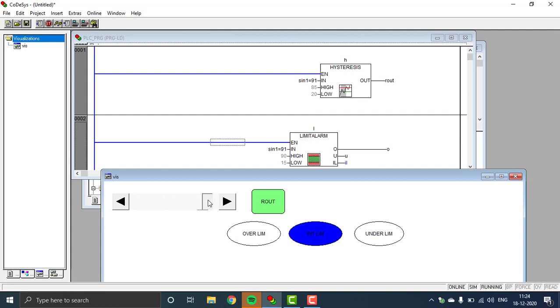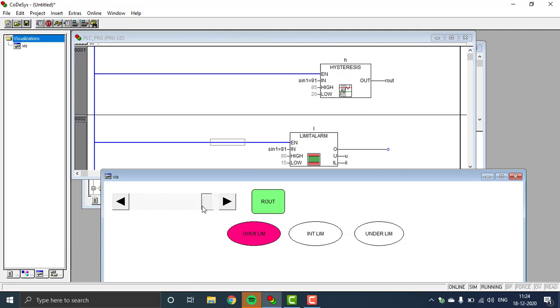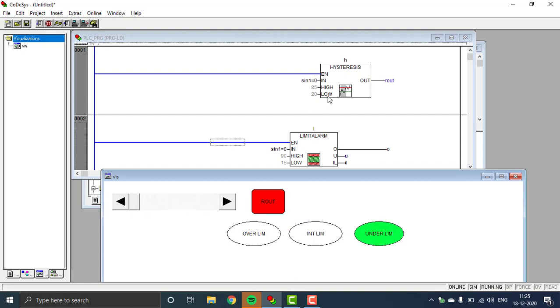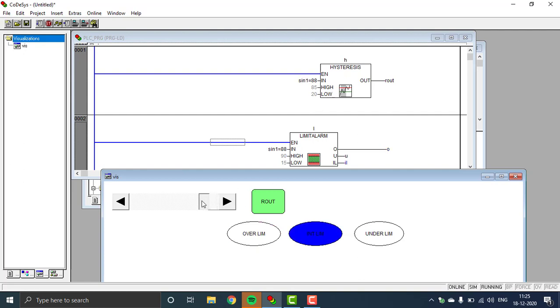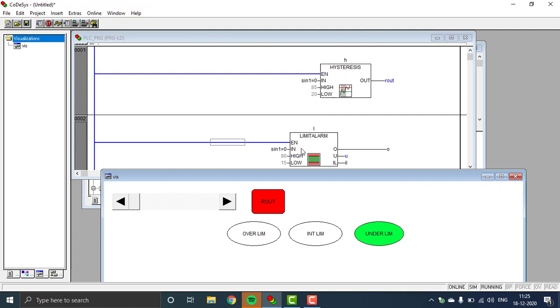Increasing to 93 and the over limit alarm has been triggered. These are all the alarm conditions and the hysteresis output for ABB with HMI visualization. You can see the intermediate limit and under limit also. The relay turns on only when the input reaches below 20 — not even in the 50s, not even in the 40s, only under the 20 limit. That is the ABB hysteresis and limit alarm with HMI visualizations. Thanks for watching.